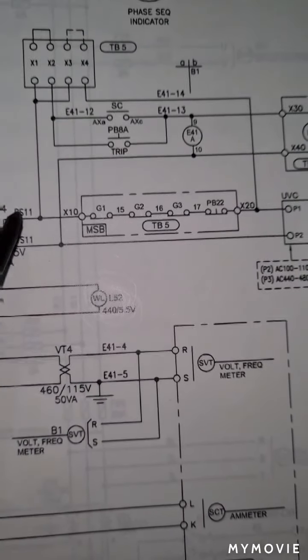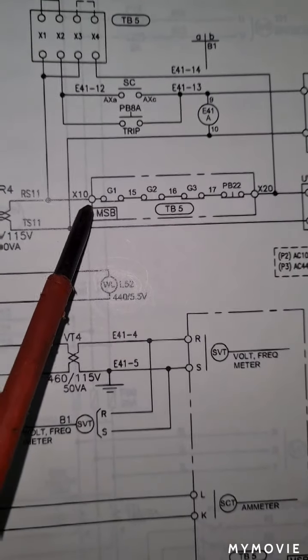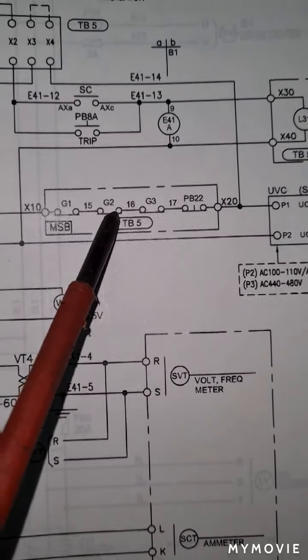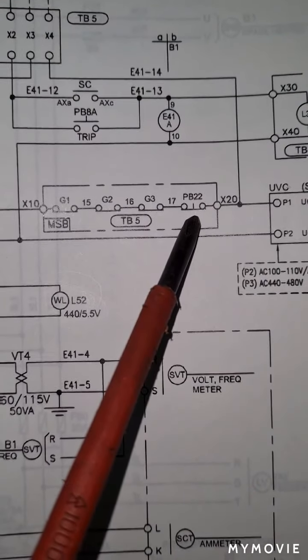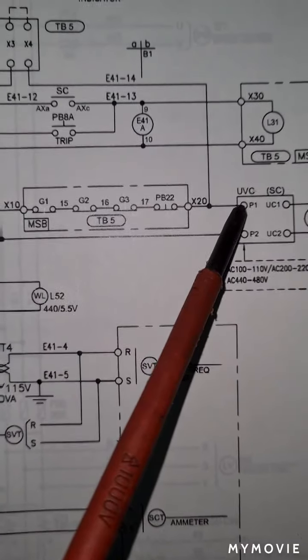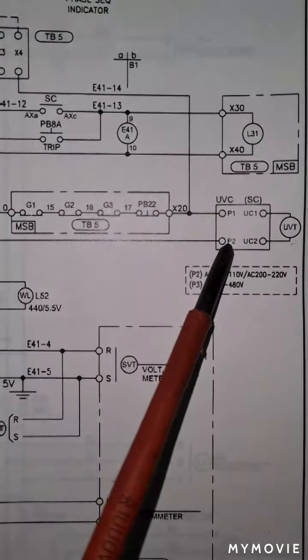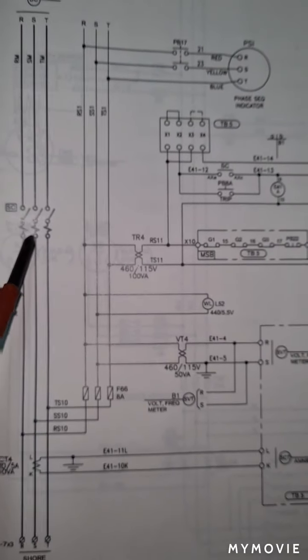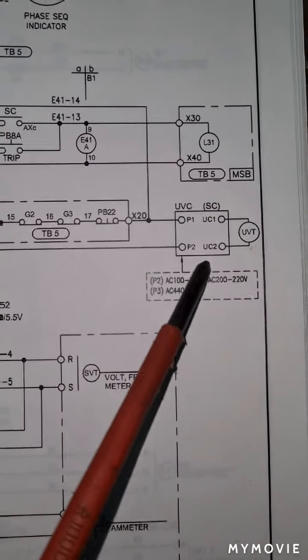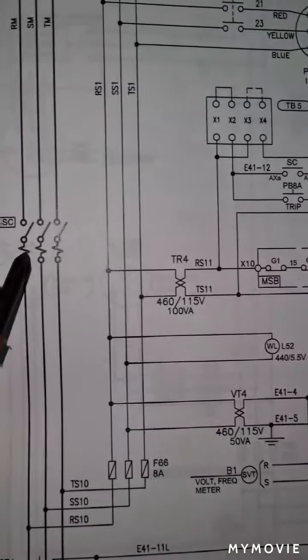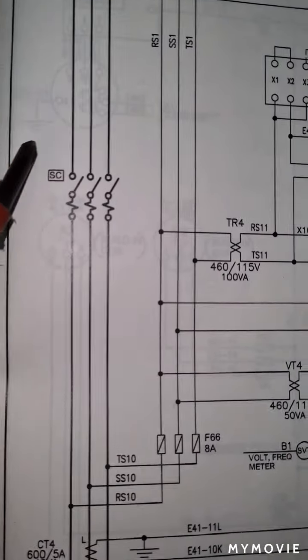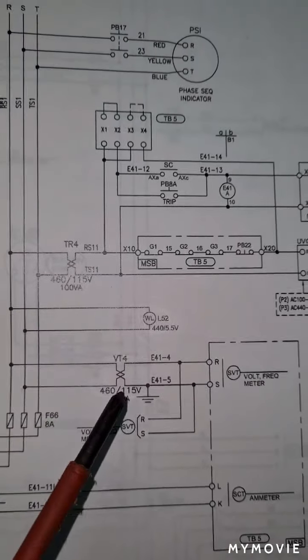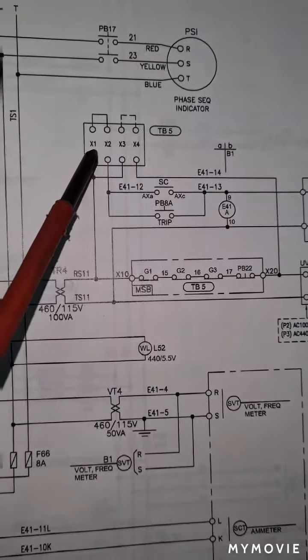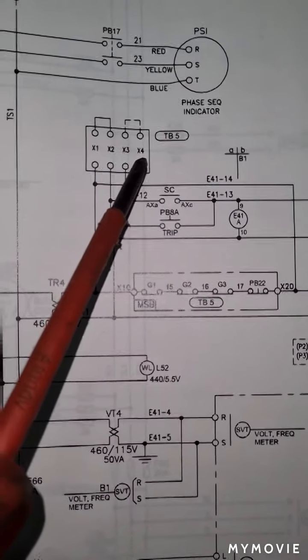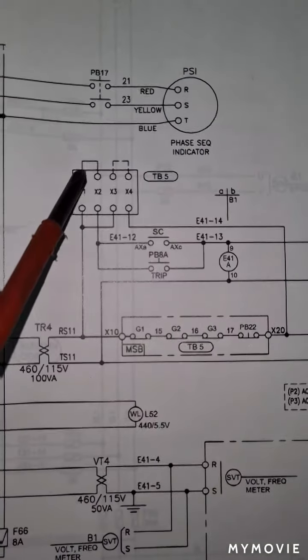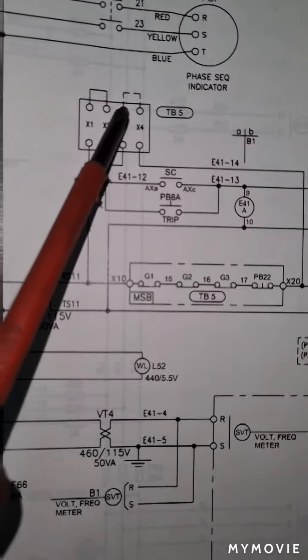Then 115 volts will complete the circuit, flowing to the normally closed contacts of the G1, G2, G3 air circuit breakers, passing to push button 22. Then it energizes the P1 and P2 of the voltage coil of your air circuit breaker on the shore connection. You must take note, without energizing this UVT or undervoltage coil, it is not possible for you to switch on the shore connection air circuit breaker. As we discussed also, we have terminals X1, X2, X3, and X4. X1 and X2 are always shorted. Then X3 and X4 are always open.